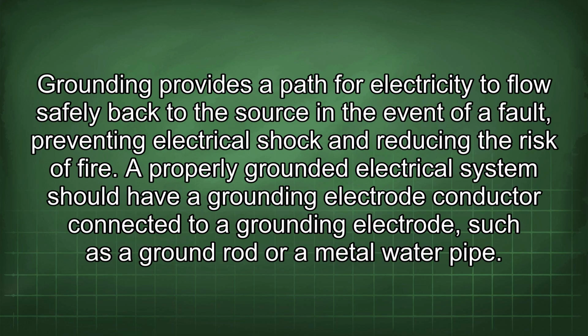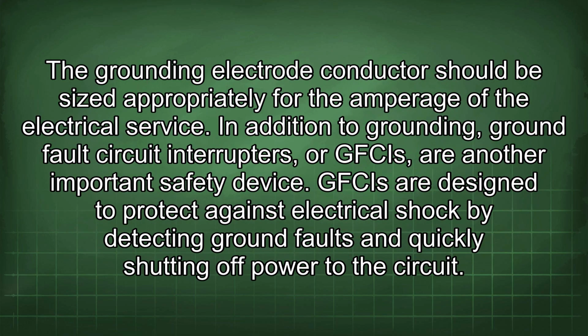Grounding provides a path for electricity to flow safely back to the source in the event of a fault, preventing electrical shock and reducing the risk of fire. A properly grounded electrical system should have a grounding electrode conductor connected to a grounding electrode, such as a ground rod or a metal water pipe. The grounding electrode conductor should be sized appropriately for the amperage of the electrical service.